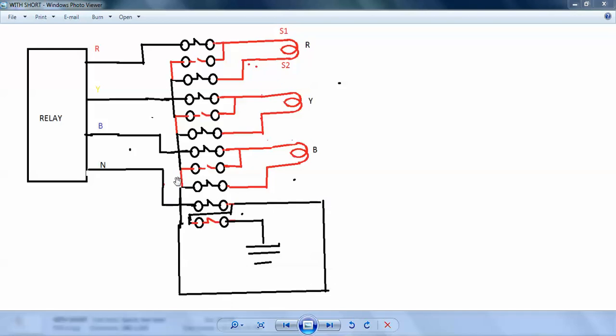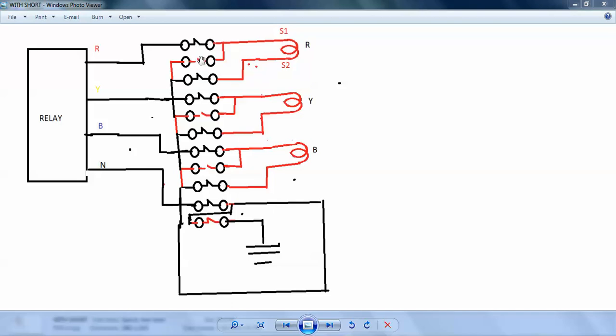Now we are going to short CT or take maintenance on this relay. What I have to do? So first of all, you have to close the links. Second, you don't open the links first. This link you have to close first, then after you have to open the link. Take care about this point. First you have to close the link, this one, then further you have to open this link. Then like this, if you want to take only R phase, just close the links, then open R phase current is zero.